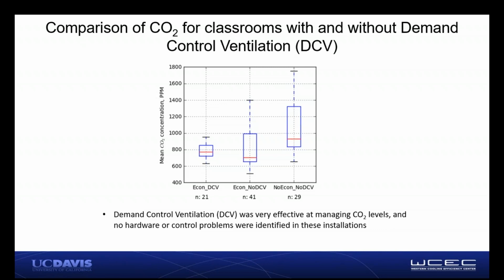You can see on the left the mean CO2 concentrations of those classrooms. The left bar represents the 21 classrooms in the study that had demand control ventilation systems, and you can see that ventilation rate hovers right around 600 to 1,000, which is really the desired range, balancing adequate ventilation with energy savings. It's possible to overventilate, though it's not that likely in a classroom just because there are so many people in there.